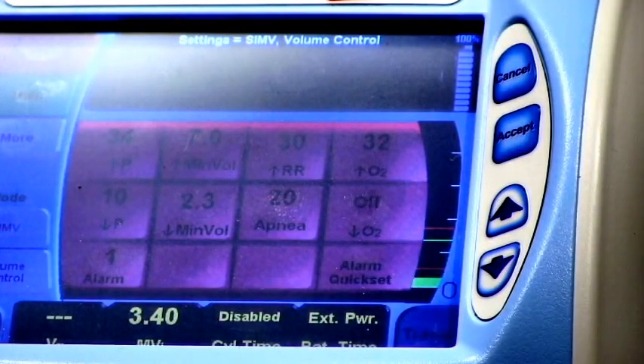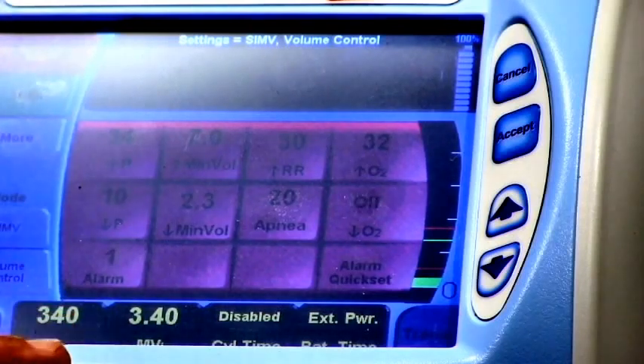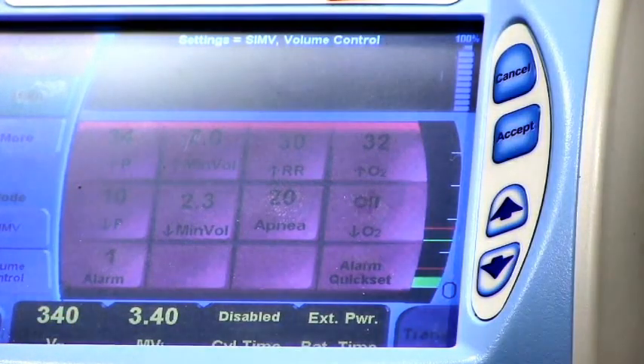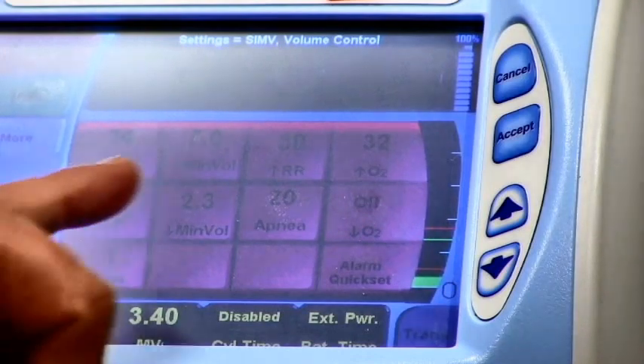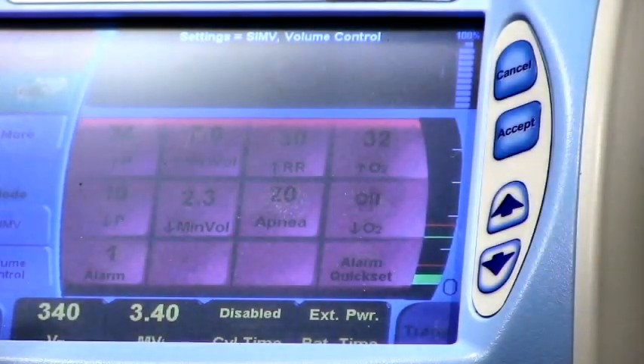The reason we do this is the alarms that are currently set are from the last patient that was on this ventilator. We have not done anything to change these alarm parameters to the new settings. So once the settings are done for the patient, we need to adjust our alarms, and in order to do so, you're going to go to the alarm screen. If for whatever reason on the mechanical lung you are getting a dark red anywhere within this screen, you must first clear that and change the parameter so it goes away and everything on the screen is pink, or alarm quick set won't work.